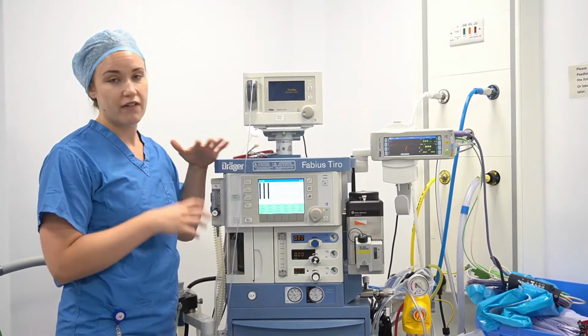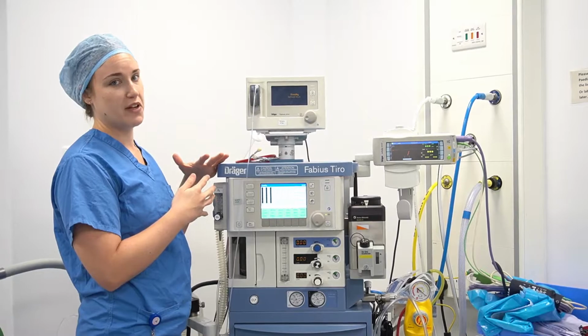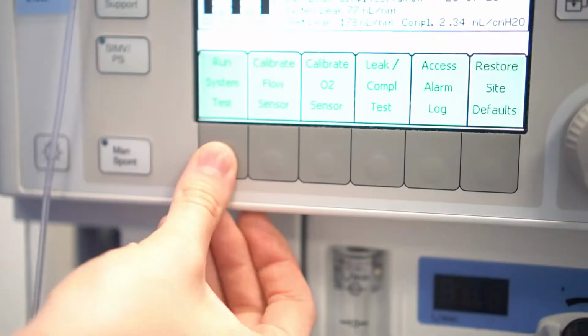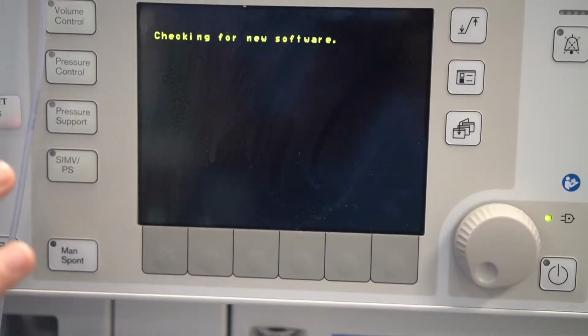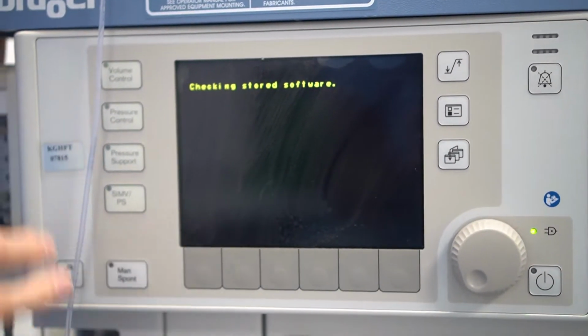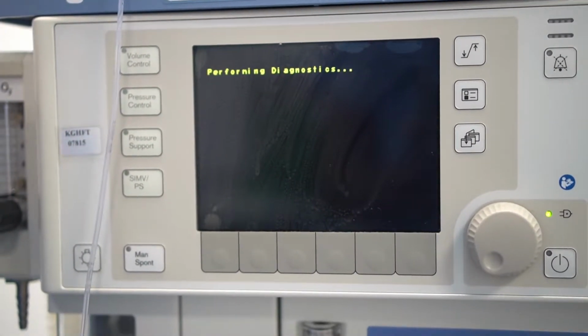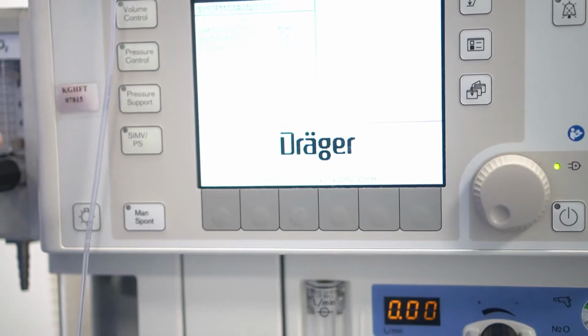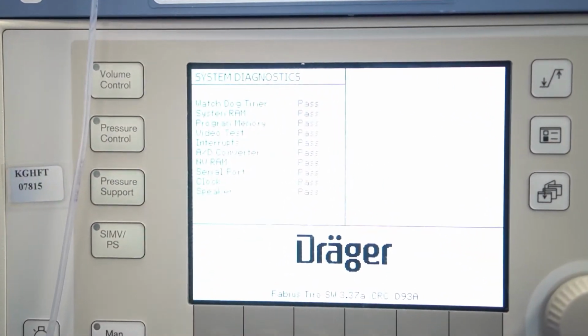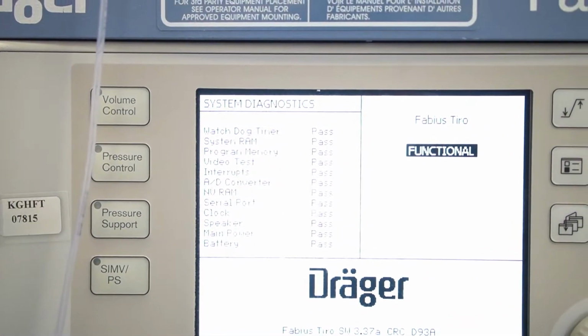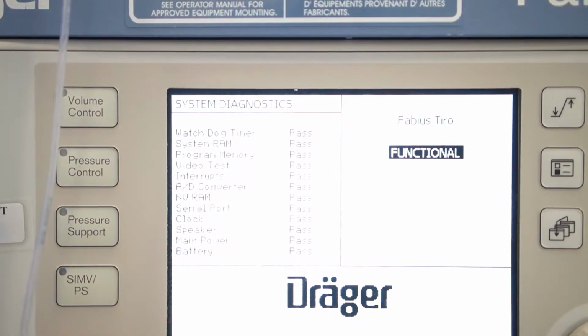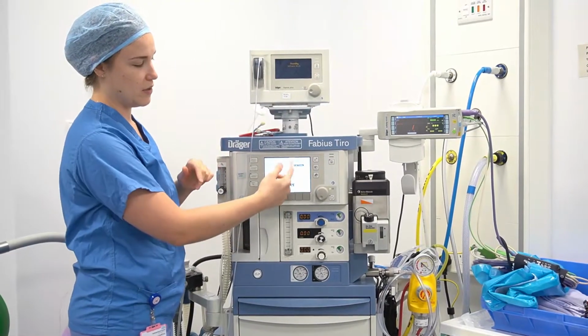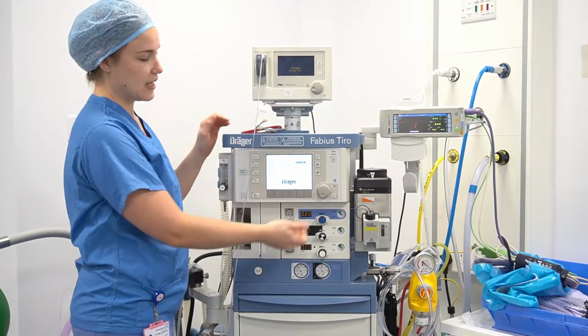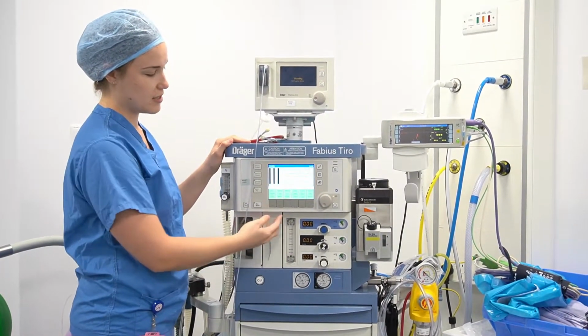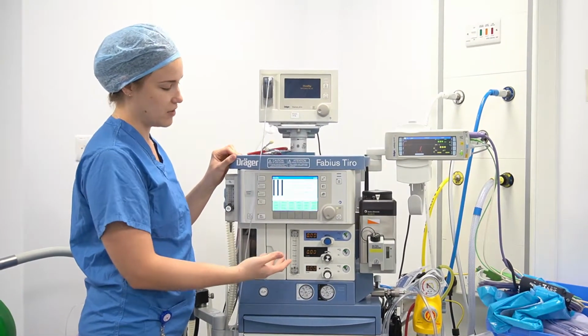Okay, so there are 5 system tests that need to be run for these machines. So we'll start with the first one. You just push the button under each specific test that you want to do. So this first one is a system test. The machine does it by itself. You don't need to do anything. It's basically just checking its software and any diagnostics that it needs to do. Then you can see it gives you a list of things that it's passed, and then it will label the machine as being functional. You can then click enter, and it will take you back to this main screen, and you can start the next one.